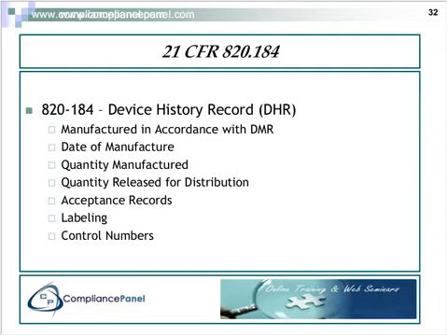And it's important that all the required information for materials is recorded so that if a recall is necessary, you'll have specific knowledge of where the affected devices are located. Now again, the level of component detail that you go to in your device history record is up to you. You can take it all the way down to a screw or a resistor on a circuit board.